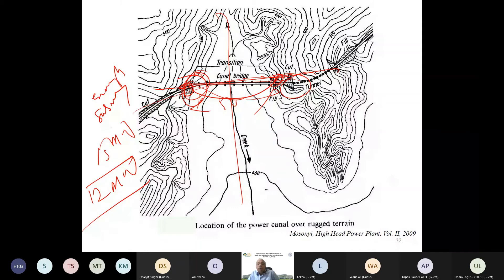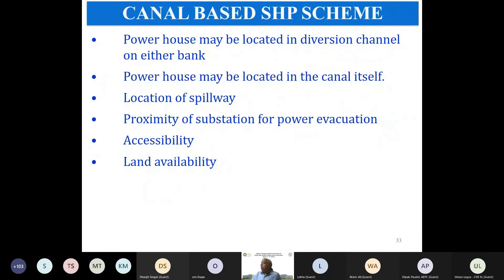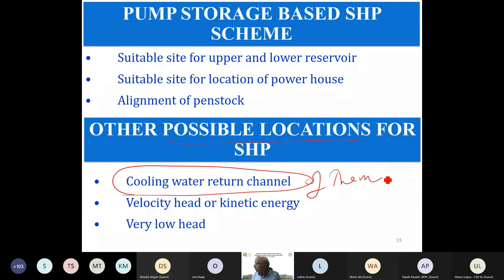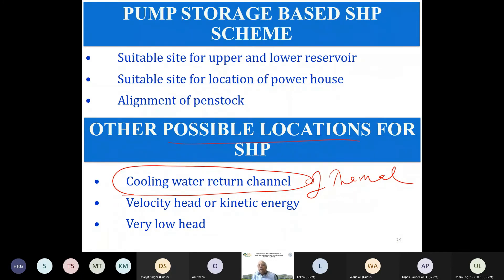Canal-based projects should be located in the diversion channel, with proximity to substations important. Dam-based schemes need suitable sites. Additionally, the return channel of thermal power plants can be used — in India, some small hydro plants have been installed on cooling water return channels of open-loop thermal plants in countries like Bangladesh, Sri Lanka, and Pakistan. These use low-head turbines such as Kaplan turbines, taking advantage of the flow velocity.